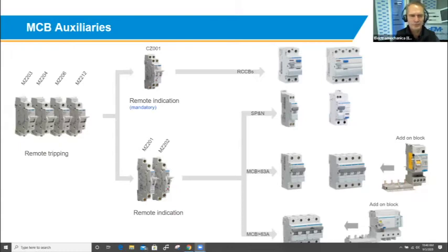The same for UVT. The UVT, where they use that mostly is in mining applications, because underground you have the possibility of methane gas, and they don't want the electrical equipment to switch automatically back on again. So you need to go down underground with a special tester, go and look for methane gas, and only when it's safe, they will switch back on this equipment. So that's where the UVT comes in handy, just for interest's sake.